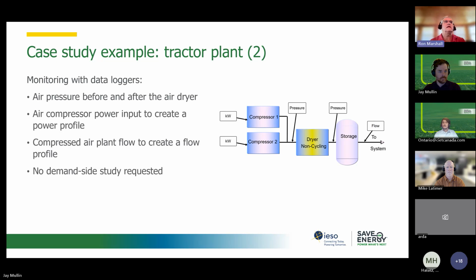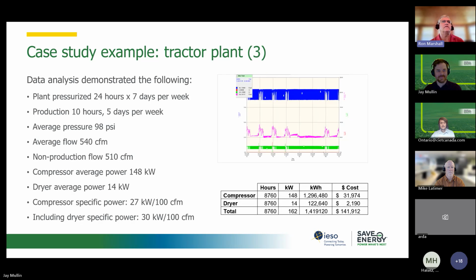So we put in data loggers, and it wasn't very fancy. Just pressure and power and flow, low cost portable data loggers. We could see pressure loss before and after the air dryer. That tells us whether things are operating nicely. We can see the pressure, the compressor power, how much is wasted, how much is actually producing air, and we can see the flow profile using a flow meter. They really didn't want a demand side study in this case, so we didn't do any pressure measurement downstream. And they have massive pipes, so there really wasn't any pressure loss across the system. Massive pipes from when this plant was putting out thousands of tractors, but now there are only a few hundred.